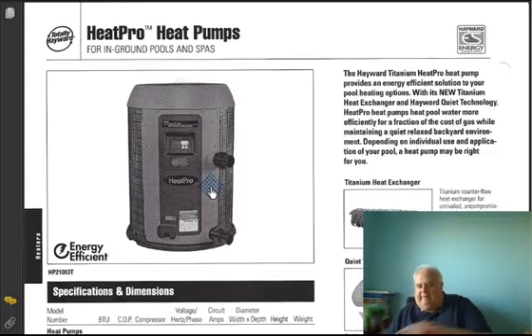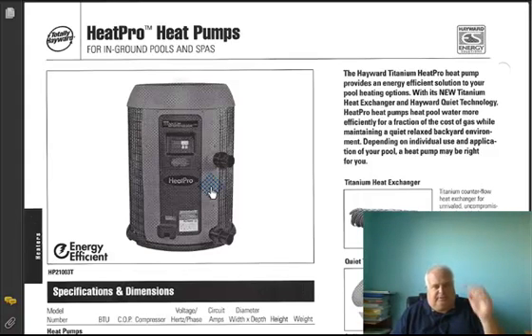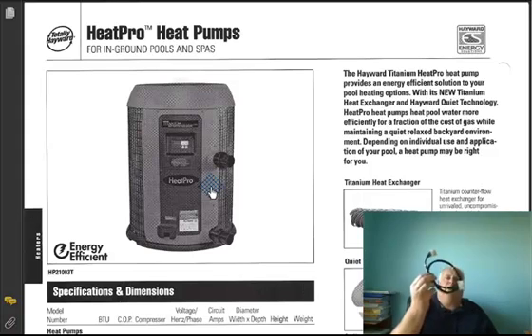So if you have an ESU unit and you're constantly going through boards, email me. This is the kit that you want. It comes with all new wiring, a little jumper board just in case. I think this is a freeze protection. Does this have a, yes, it has freeze protection, so that's probably why it has a jumper. So anyway, you've got the new interface board that you snap on, you got your new cord, and you got your new board, and it'll fit in your ESU unit.